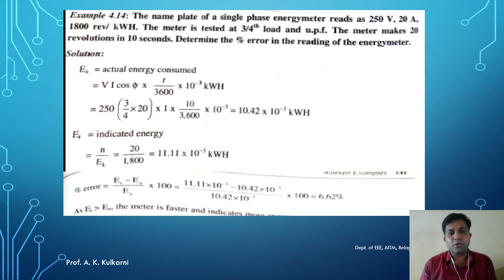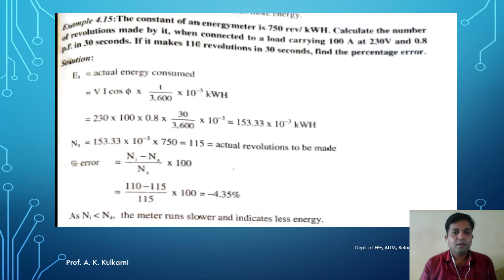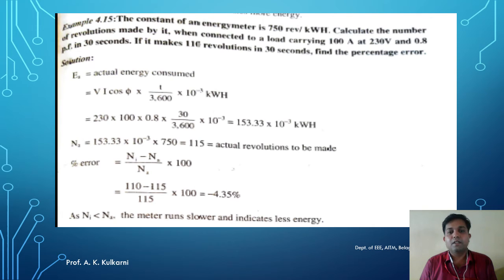Now let us solve a similar problem. The constant of an energy meter is 750 revolutions per kilowatt hour. Calculate the number of revolutions made by it when connected to a load carrying 100 ampere at 230 volts and 0.8 power factor in 30 seconds. If it makes 110 revolutions in 30 seconds, find the percentage error.